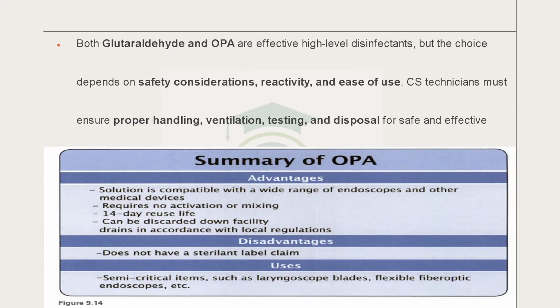14-day reuse life. Yes, you remember that I was talking about 14 to 28 days. The 14 days is very popular, accepted, even though the claim can be given as 28, but the manufacturers are almost always very specific about the number of days. Yes, can be discarded down the facility drain. Easily, we just put it away when we're using the manual method, but now with machines, the machines will just flush it out.